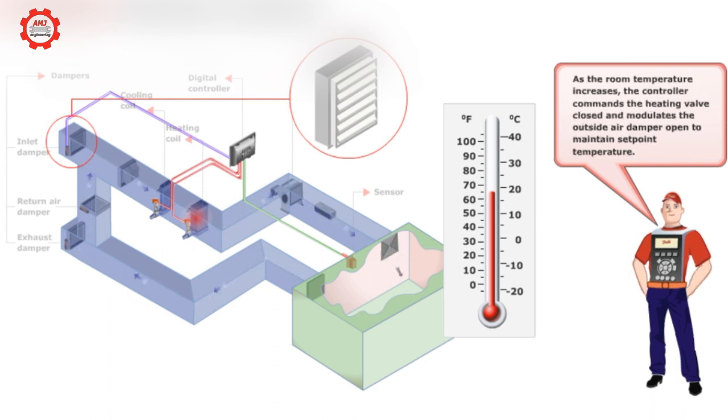As the room temperature increases, the controller commands the heating valve closed and modulates the outside air damper open to maintain set point temperature.